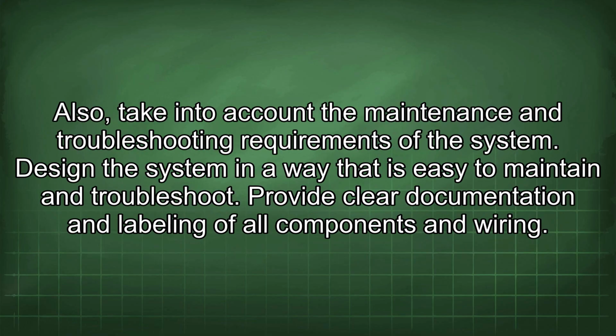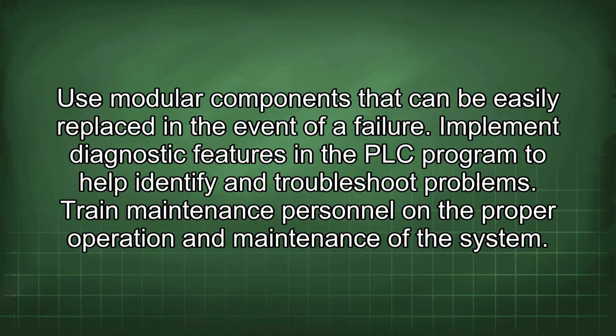Also, take into account the maintenance and troubleshooting requirements of the system. Design the system in a way that is easy to maintain and troubleshoot. Provide clear documentation and labeling of all components and wiring. Use modular components that can be easily replaced in the event of a failure. Implement diagnostic features in the PLC program to help identify and troubleshoot problems. Train maintenance personnel on the proper operation and maintenance of the system.